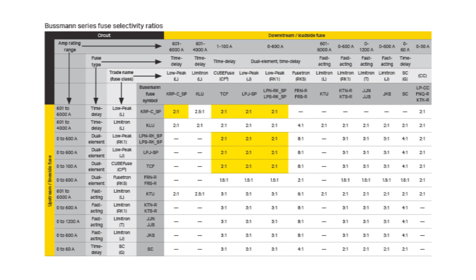While important, selecting overcurrent protected devices based solely on their ability to carry system load current and interrupting the maximum fault current at their respective application points is not enough. As the demand for power system reliability increases, the overcurrent protective device's performance becomes more critical, as its function should ideally limit system outage to only that portion of the circuit which is faulted. The selected overcurrent protective device types and ratings determine whether they are selectively coordinated upstream, such that only the nearest upstream device will open for the full range of overcurrents and opening times. This leaves the remainder of the system undisturbed to preserve service continuity.